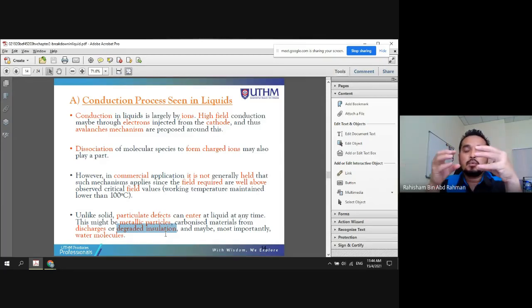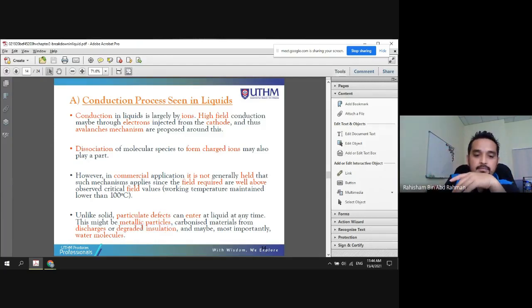Once we have the metallic particle, when this small particle comes to the high voltage terminal, it can somehow trigger discharge activity within the liquid dielectric. Although it is small scale, with time, the transformer oil will become degraded, meaning its dielectric strength will be reduced and it will need to be replaced. That is how premature degradation occurs within the liquid dielectric.